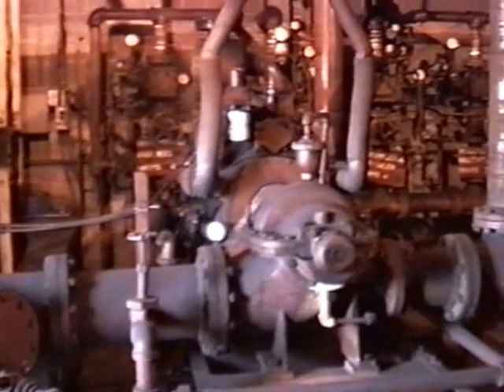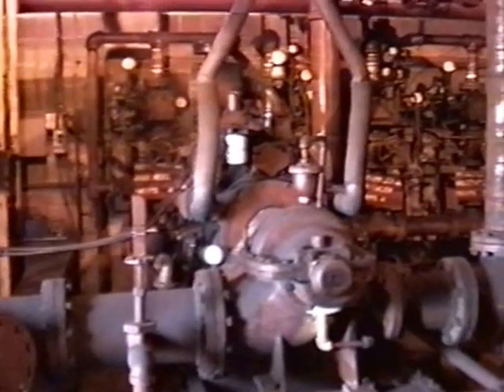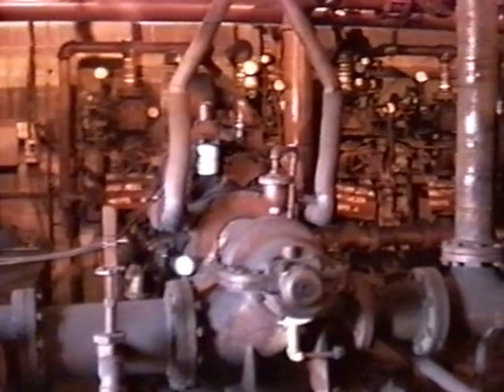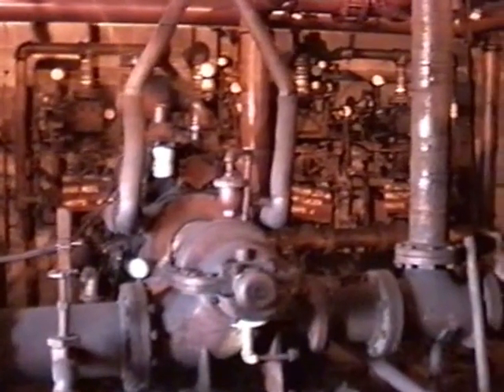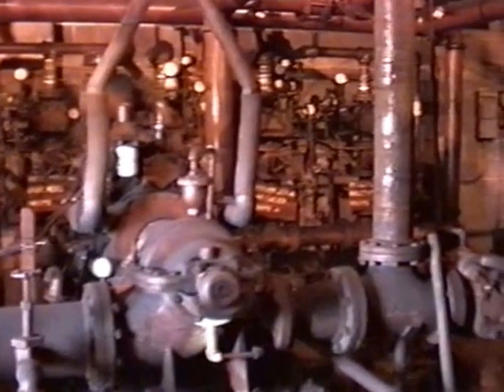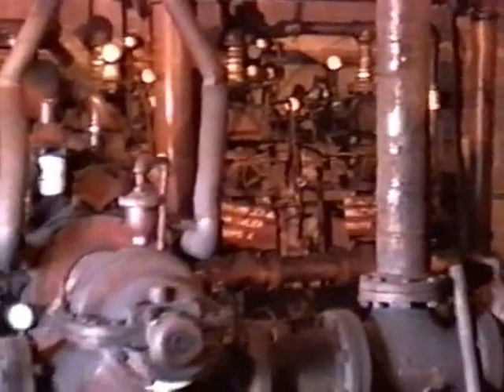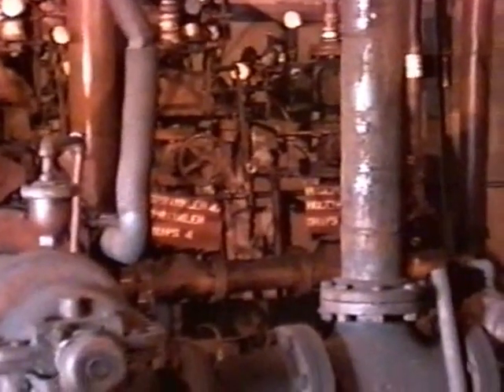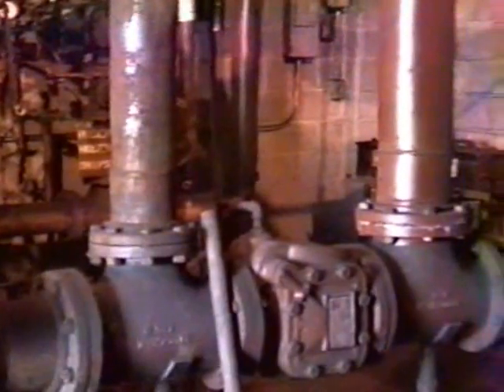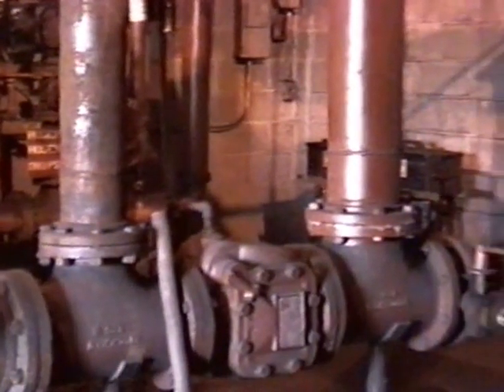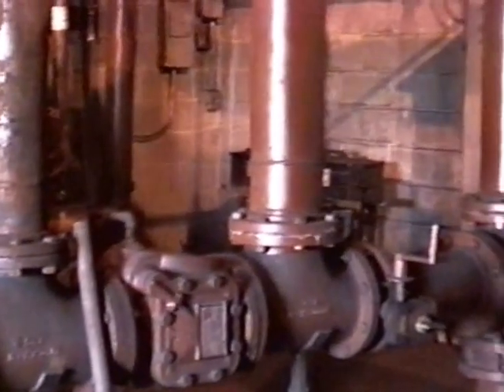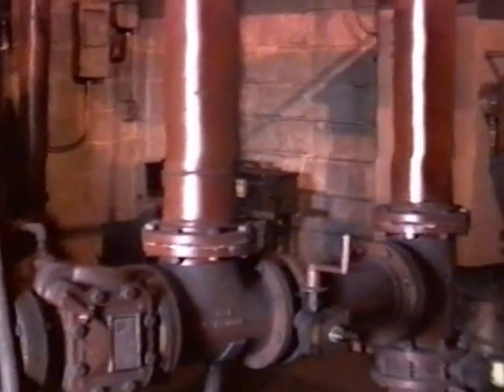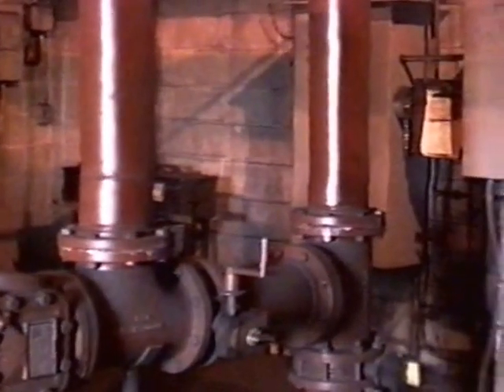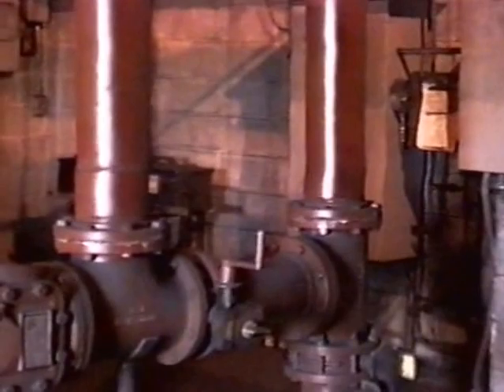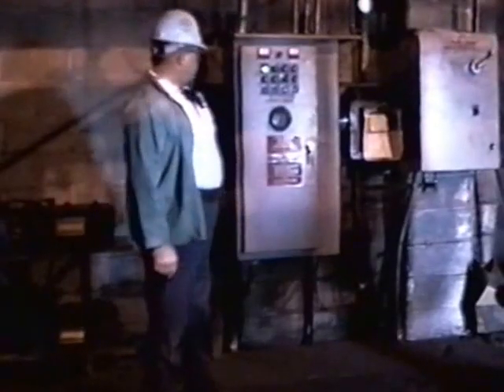The diesel fire pump has in the building sprinkler systems and deluge valves for the hose reels that we just saw up in the junction house. These are the two inside ones. The deluge systems are the outside ones. The system is operated by our controller over on the far wall. Let's take a look at that. It's operated by this controller.